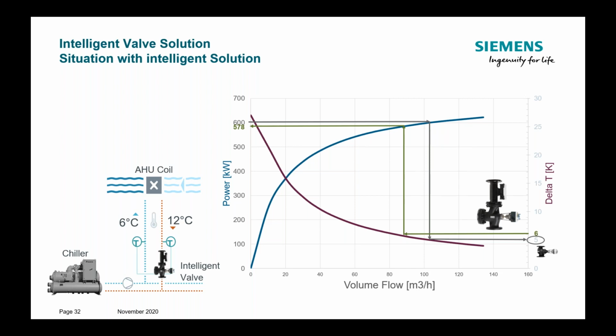97, 98 cubic meters, and it will result in only a slight decrease of the power transmission of this coil, because on the one hand we have decreased flow, but on the other hand we have increased DeltaT. So we still provide the right power to this coil to do its job, to transmit the right energy to the air handling unit. And this flow limitation we see here, from 103 to 90 cubic meters, this more than 10% flow limitation, only results in 2 to 3% less power, as you see on the left-hand side.